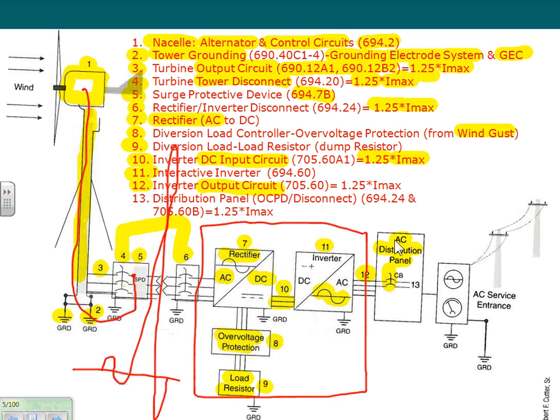You tie it to the main distribution panel, and look how they size it. Again, you keep repeating, really not a whole lot in it. You take the maximum current coming out of the inverter, multiply by 1.25, and then you size your conductors. If you're indoor, we'll talk about this, number 12, yeah, number 12 is a big deal. As you bring the conductors from the inverter, and say the inverter is outdoor and I'm pulling these conductors into the building, I have to put them in a conduit. They have to be in some type of conduit until you reach the disconnect right in here. When you reach the disconnect, then you can use any wiring system after, cables and so forth.